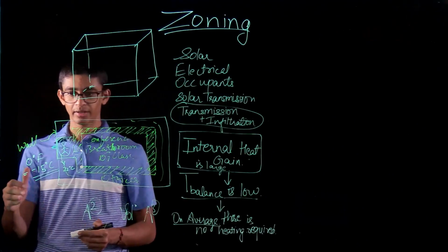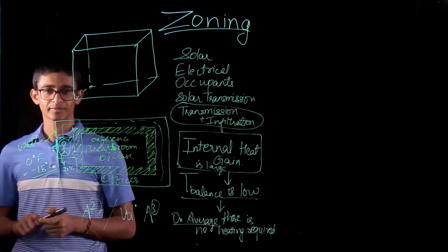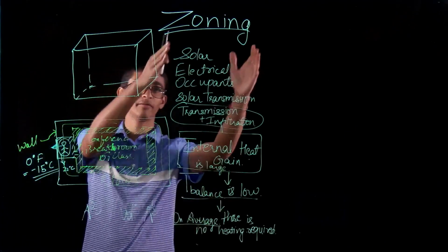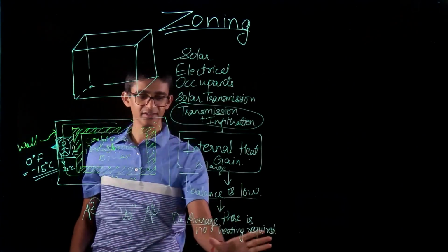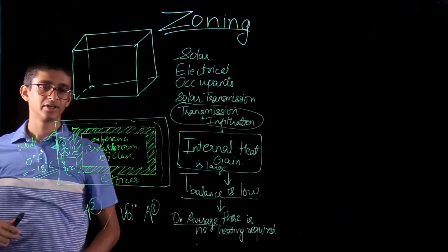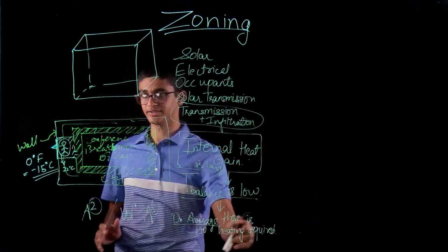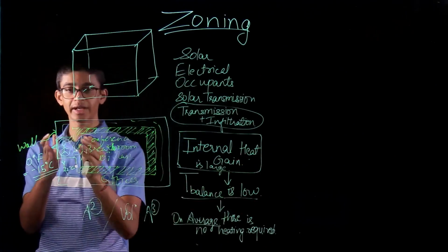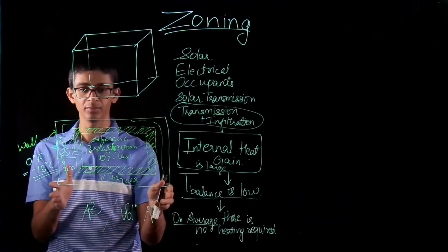And as the time goes by, this temperature will drop. But when we do all the analysis on average loads, it says there is no heating requirement, but eventually this room will require heating. Hence, this is an anomaly. This is a problem of considering the average loads. When we consider the average load, we do not get the actual requirement of a room. We are getting an overall requirement of the whole building.